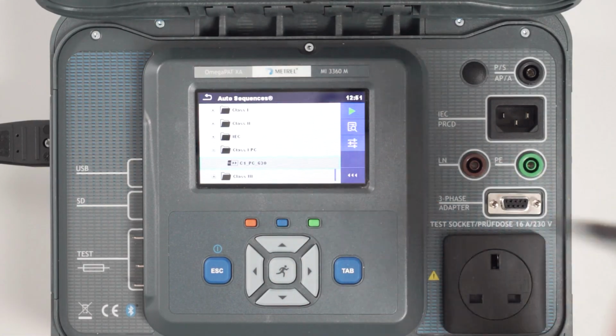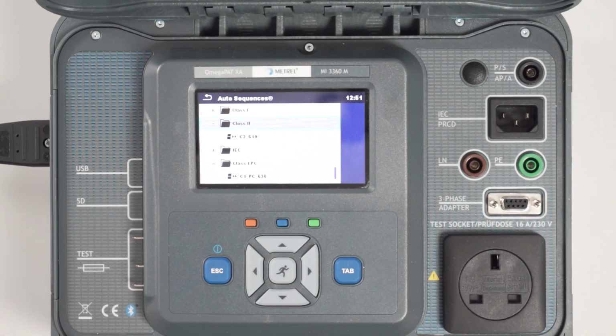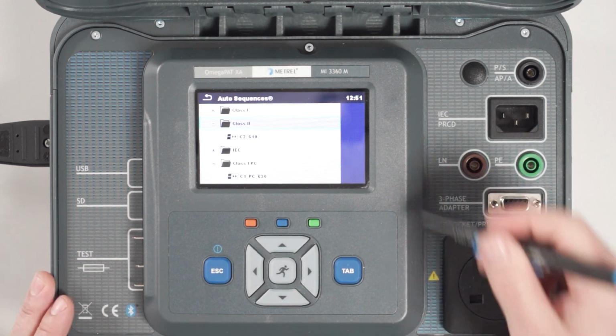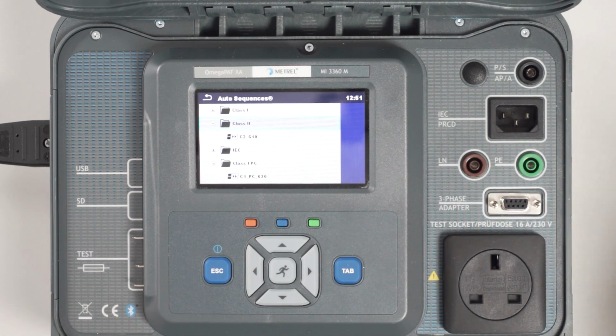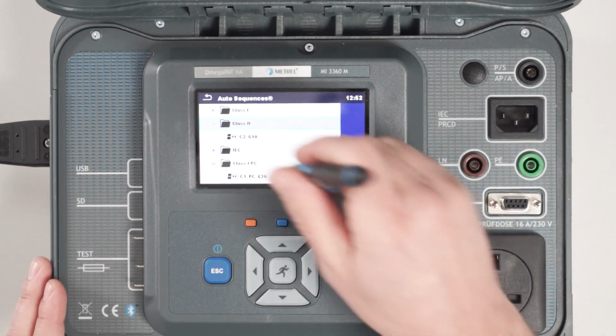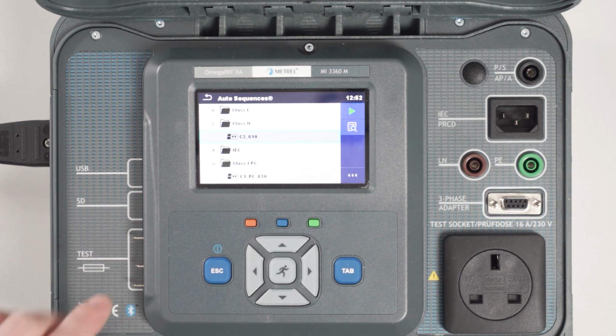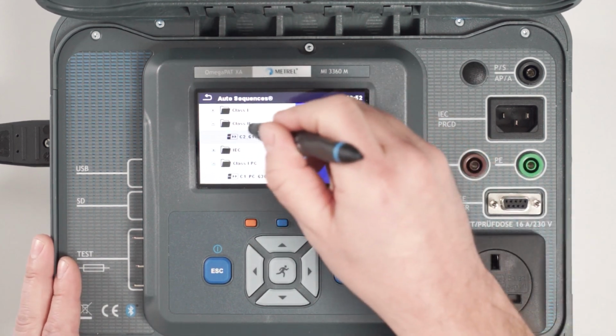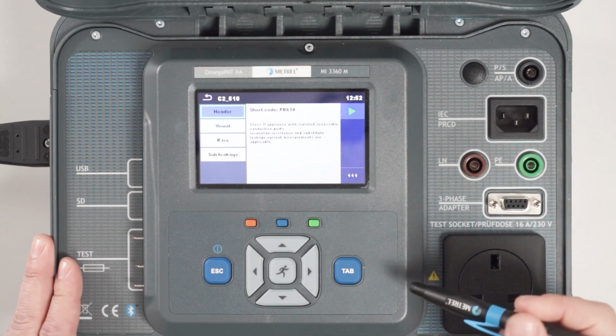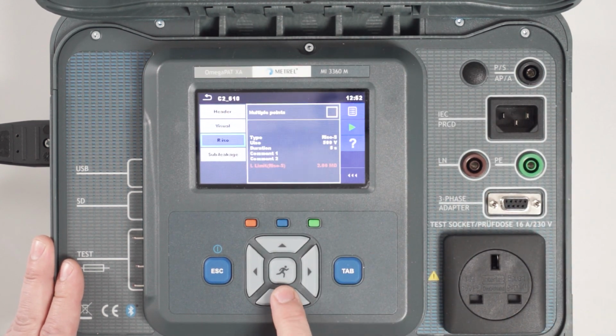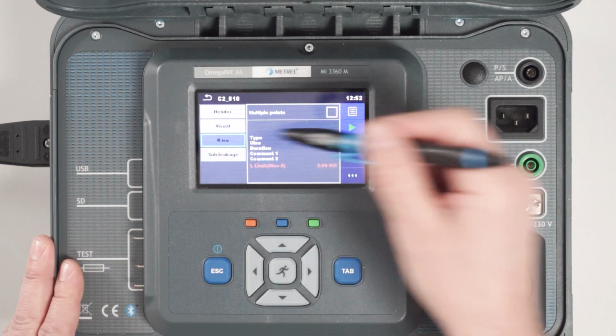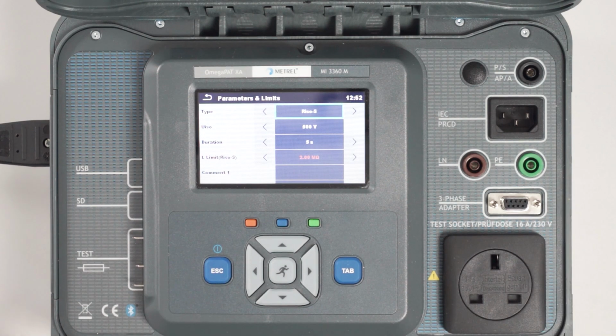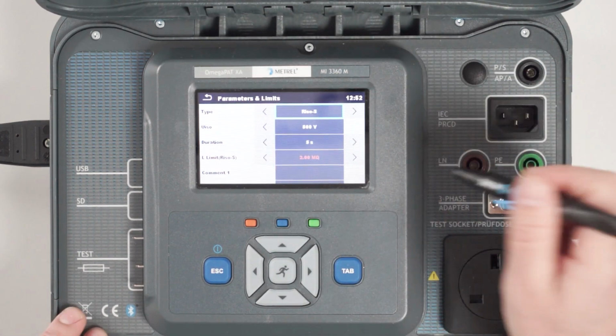Once we start one of these auto sequences, let me, for example, start the auto sequence for class 2, because we will be able to finish it as we don't need anything to connect. So we select class 2 appliance, auto sequence for class 2 appliance. Again, we have the option here to change parameters of this auto sequence, so we can go inside insulation resistance test, click on the center of the screen and adjust different parameters.